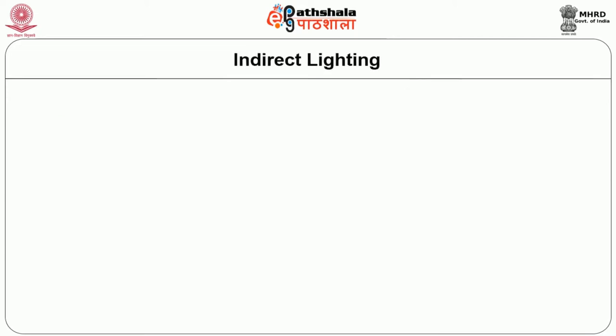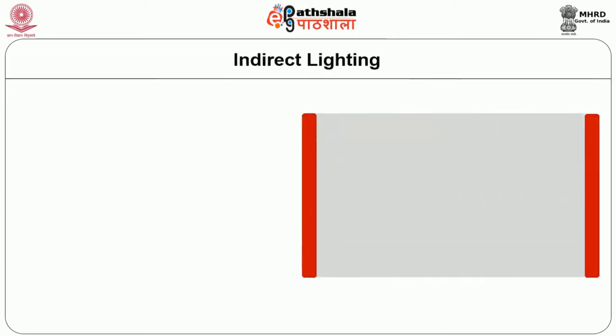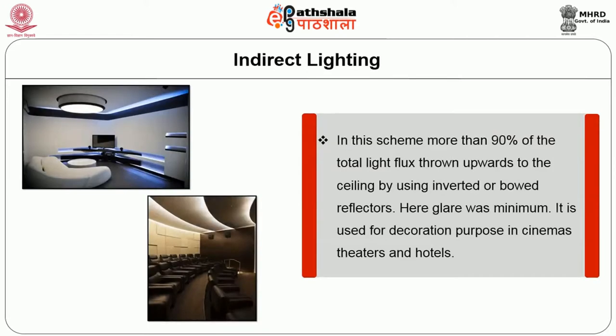Indirect lighting: in this scheme, more than 90% of total light flux is thrown upwards to the ceiling by using inverted or bowl-shaped reflectors. Here, glare is minimum. It is used for decoration purposes in cinema theaters and hotels.